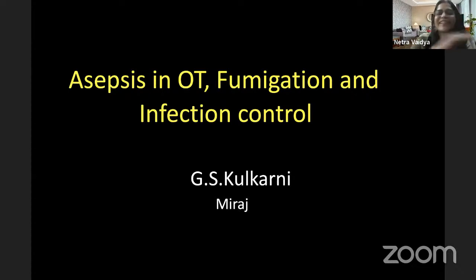In my younger age, when I started in the CSSD, we used to have those drums. You used to open it, and then post sterilization in your sterile area, we had a sterile area. So in your open area, where we do not know what the air count or microbial count of that particular area is, you're closing it. So there are chances of some air having gone inside the drum. That's how, once you open the drum, it becomes unsterile. So use it only once. You keep it for a day or whatever time frame, which once again you need to calculate. How much time you are going to keep it. But once you open it, you just have to treat it as unsterile.